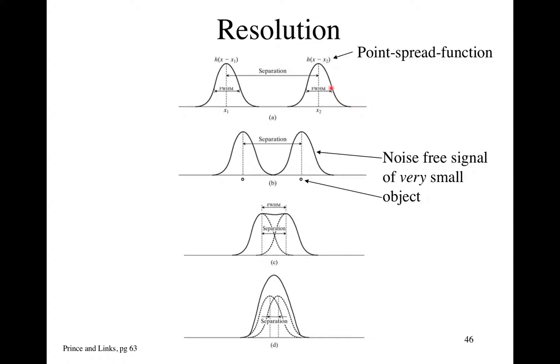If this width gets wider for different systems, that means it's a lower-resolution system — it blurs that signal into a broader spatial distribution. If it's really sharp and narrow, it's a high-resolution system. The Rayleigh criterion is developed by taking two of these dots, bringing them close together, and asking when you can no longer perceive that you have two dots and see just one signal — that's another definition of spatial resolution.